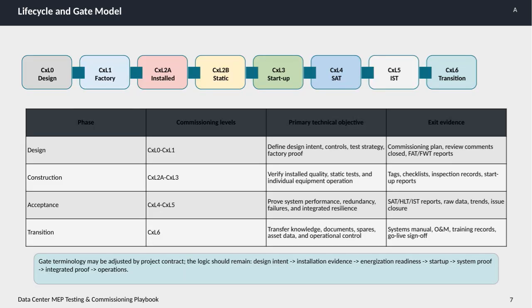Here we have an overview of the lifecycle and gate model for data center MEP testing and commissioning. The process is divided into distinct phases, each with specific commissioning levels, objectives, and exit criteria. Starting with the design phase, labeled from CxL0 to CxL1, the main goal here is to establish the design intent, controls, and testing strategy, as well as conduct factory-proof testing. The exit evidence for this phase includes the commissioning plan, completed review comments, and factory acceptance or witness test reports.